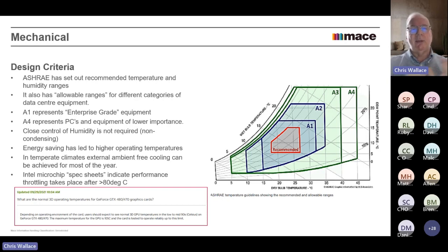Mechanical, right, okay. This is just a cut from what ASHRAE would say, where you need to be within that little recommended zone in the center. And then the A1, A2, A3, A4 are different levels of equipment. A1's enterprise grade equipment, and A4 is probably just PCs and lower importance equipment. What they're saying is humidity, as long as it's non-condensing, is not really a drama. And obviously what's happened over the years is we've started to creep up from it being just an 18-20 C environment, which we thought was keeping everything cool and sweet.